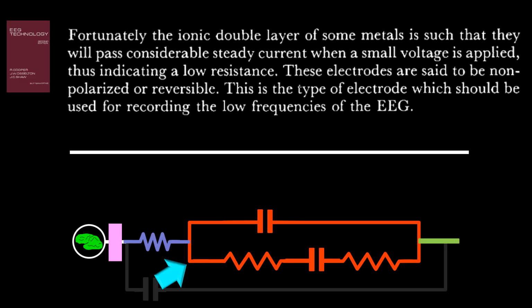In the other leg we see the resistor, implying a straight resistance of the electrolyte electrode interface, followed by a capacitor and a resistor. These two elements, that is the capacitor and the resistor, represent Warburg impedance. The green line represents the outgoing segment of the circuit, and the gray line with the symbol for a capacitor implies stray capacitance. That is, the unavoidable capacitance produced by circulating electricity.